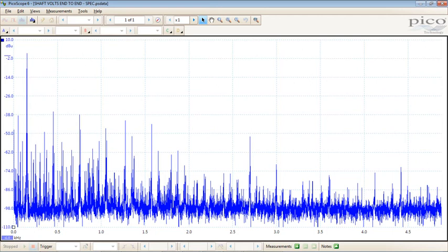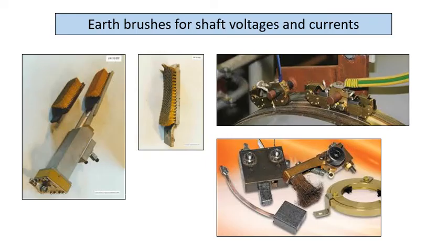There's your 50 hertz, and these are your higher 400s and about 750. So that's typically your magnetic noise that you hear in a machine. So that's your slot harmonic interaction. This is on a decibel scale. That's around about 0, and this is about 30 dBs down. So it's massive. It's predominantly 150 hertz. The conclusion I came to is it's not related to a third harmonic. It's related to interaction between the number of magnetic asymmetries that exist in the rotor, multiplying your 50 hertz by a certain amount. And incidentally, the other motor shaft voltage is about 200 millivolts.